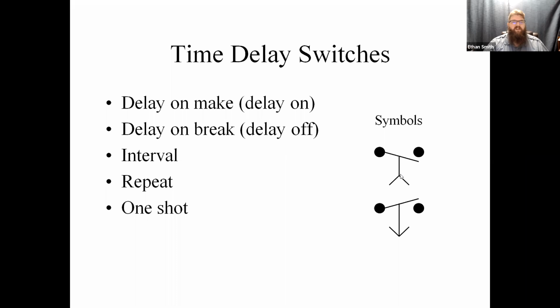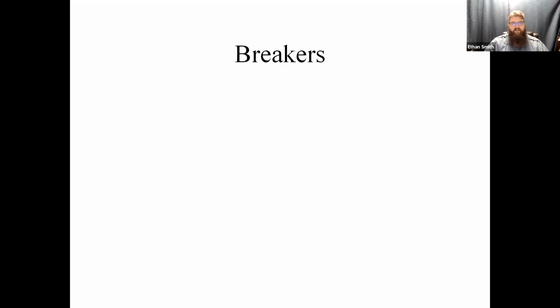The trick with time delay switches is you not only have the switch to diagnose, you also have the time component to diagnose. So this is where a stopwatch comes in real handy, because I don't know about you, but standing in front of something, waiting for something to activate, time stretches off into eternity. 30 seconds becomes 5 minutes, and I can't trust myself. So I used to do this a lot with ice machines. I had a stopwatch that I hung on the unit so that I could sit there and time defrost cycles or time harvest cycles or anything like that, because those were time critical devices. There were a lot of time delays in them. And the only way to test a time delay switch is to activate it and see if the timing's correct. Okay. But again, they're switches.